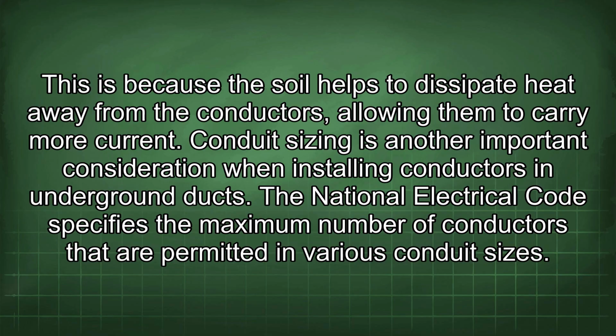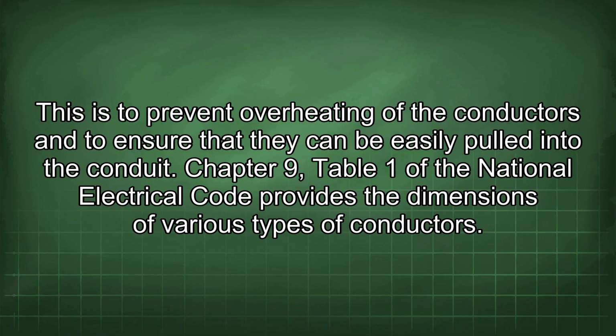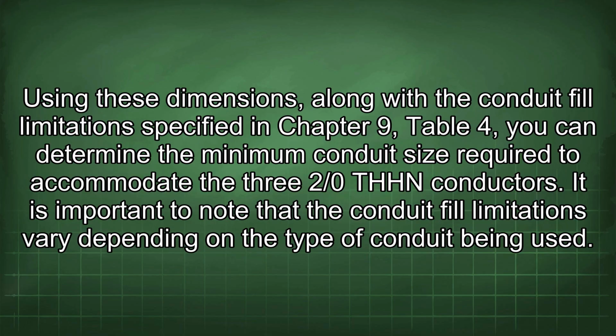Conduit sizing is another important consideration when installing conductors in underground ducts. The National Electrical Code specifies the maximum number of conductors that are permitted in various conduit sizes. This is to prevent overheating of the conductors and to ensure that they can be easily pulled into the conduit. Chapter 9, Table 1 of the National Electrical Code provides the dimensions of various types of conductors. Using these dimensions, along with the conduit fill limitations specified in Chapter 9, Table 4, you can determine the minimum conduit size required to accommodate the 3 2/0 THHN conductors.